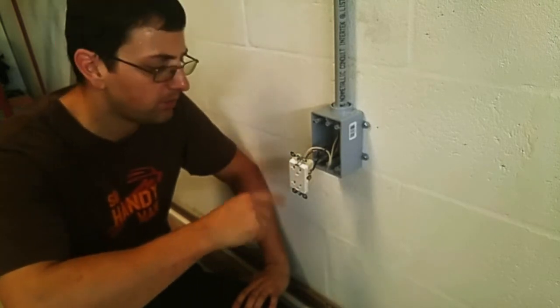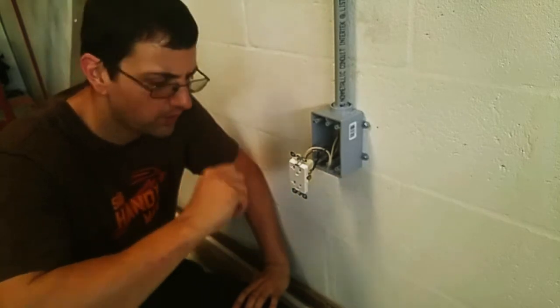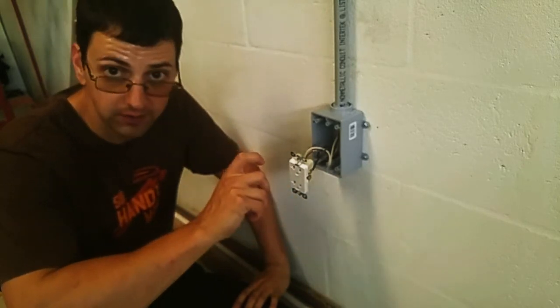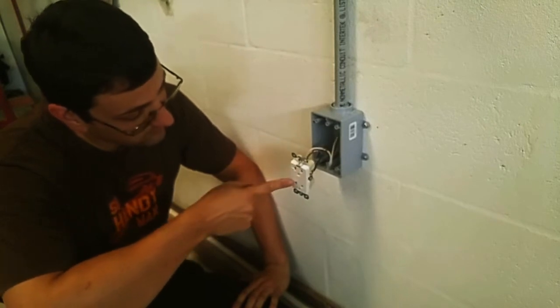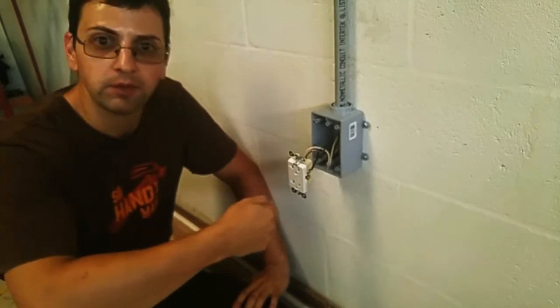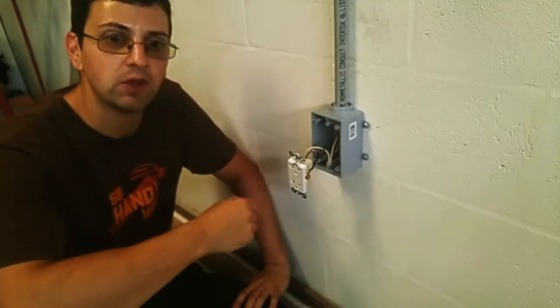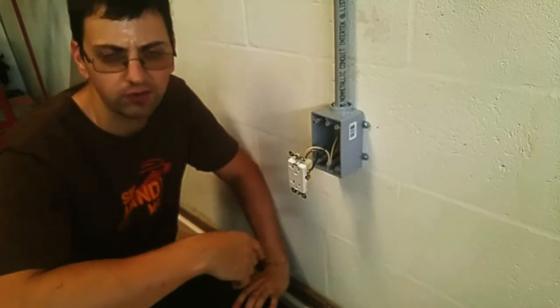If I had something plugged in the top, that's two sources of increased resistance. However, by staggering it with the hot connected on this terminal, the neutral connected here, no matter where I plug something, I know I'm only going through one source of greater resistance. It's just good practice.